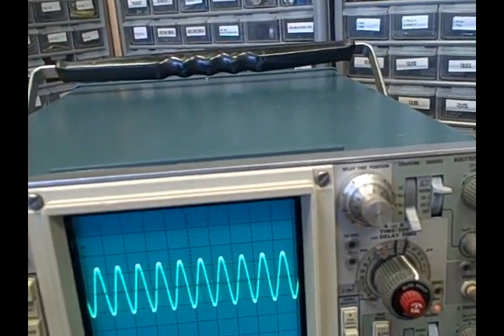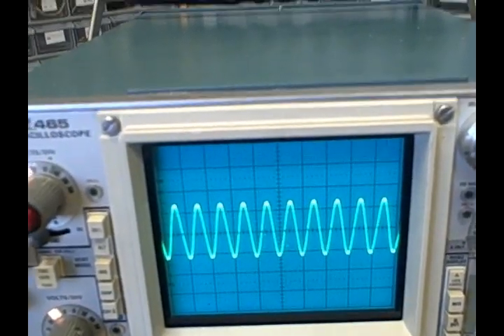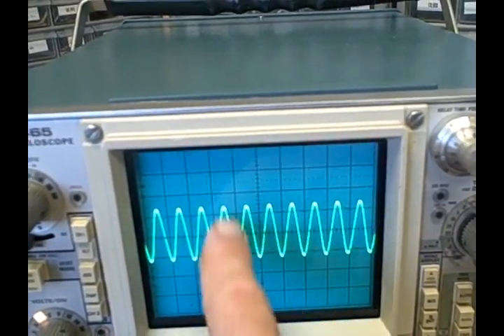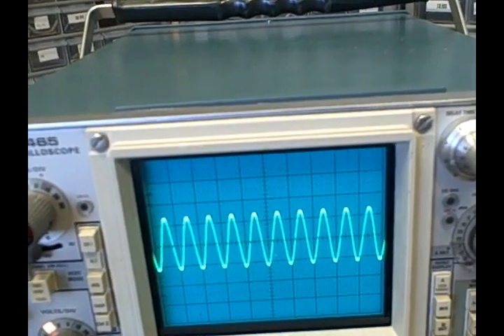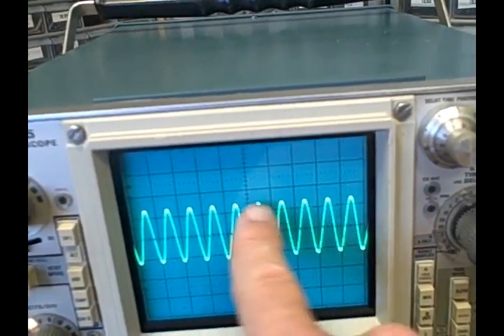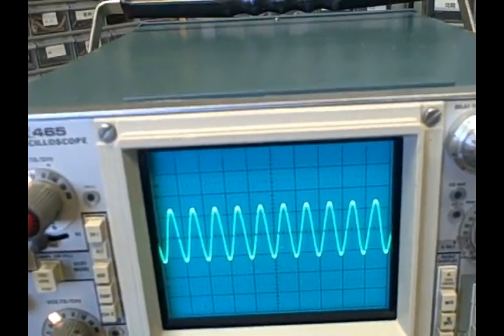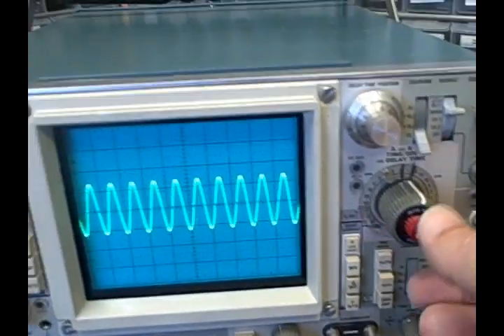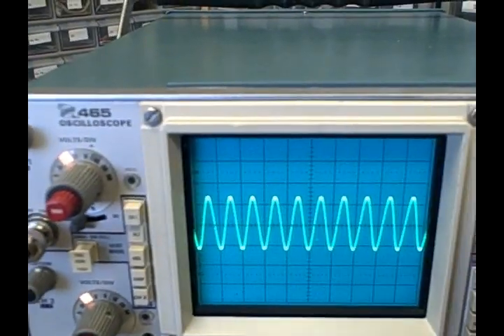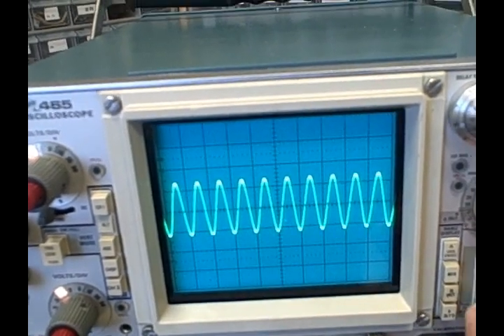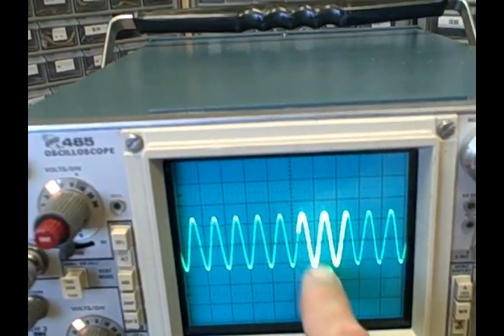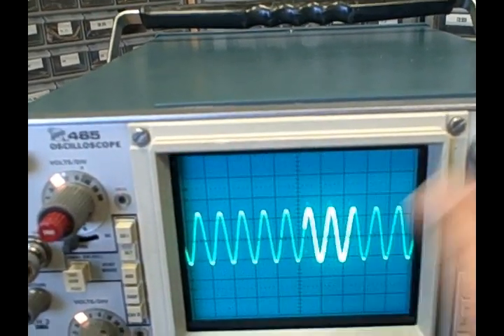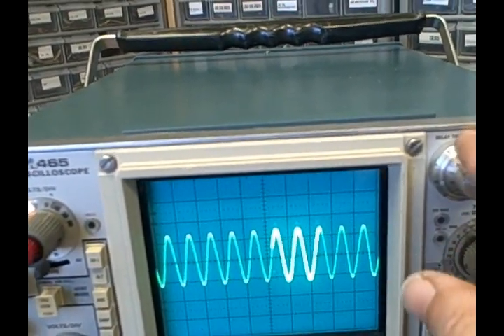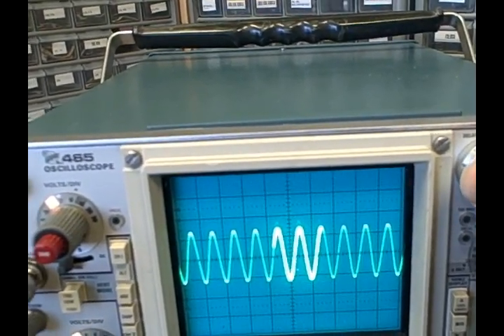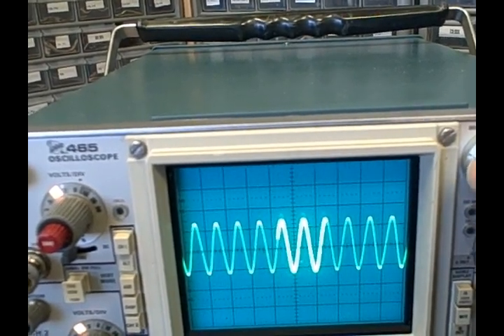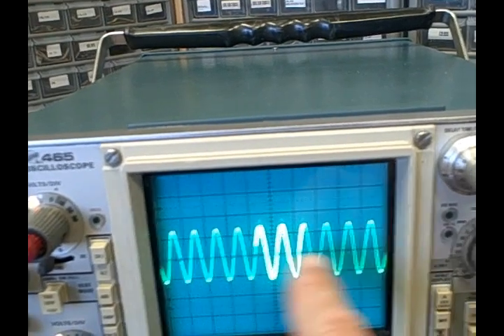We are going to input 10 megahertz into here. And I'm going to, after 1, 2, 3, 4, after the fourth cycle of the waveform, I want to see what is in the middle here expanded. I want to get a closer look at it. Well, I can do that because of the second time base that's on this unit. So right now we are looking at the main time base, so just straight time. You see this highlighted portion here. You can't miss it really. 1, 2, 3, 4. I want to move that highlighted portion by moving this time delay knob up here to the fourth cycle. So let's see. Right about there. So after the fourth cycle, I want to expand that region.